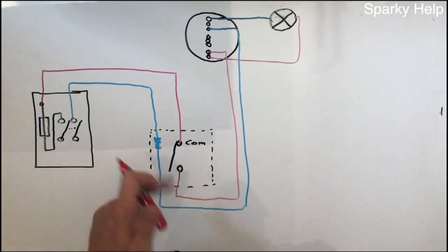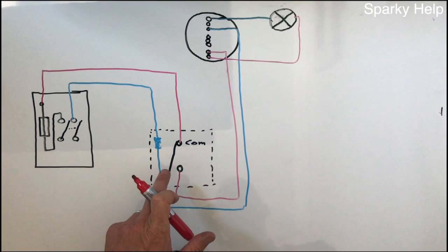So now when wired we have a twin and earth that comes into the box and we have a twin and earth which comes out of the box. When taking these twin and earth to these points here, you need to mark which cable is going where, so we need to mark the switch line cable going back up to the light.